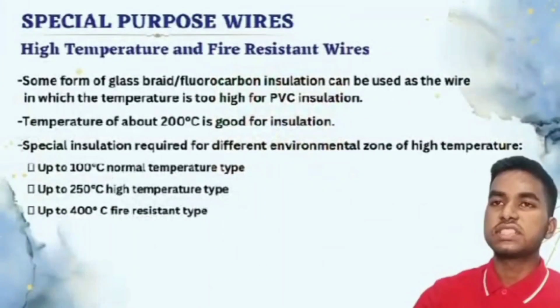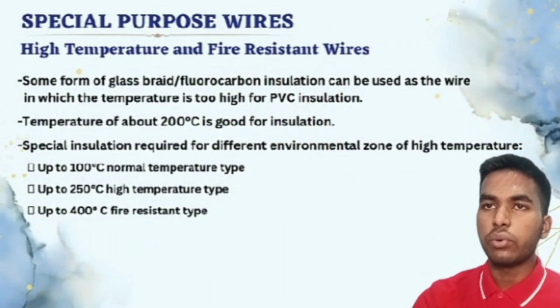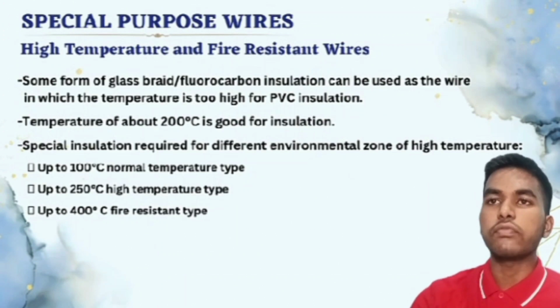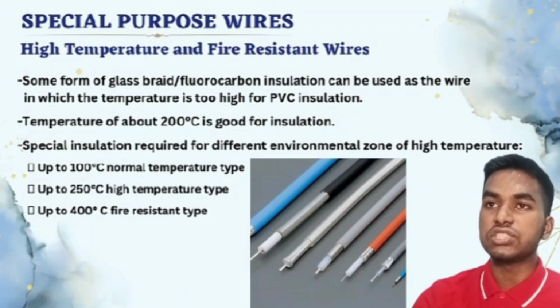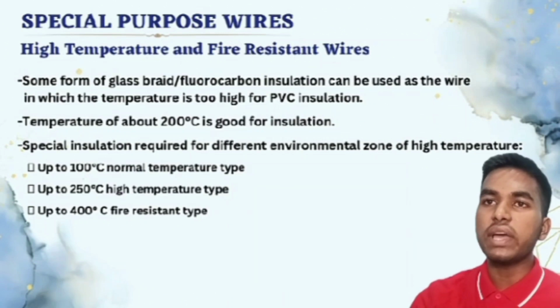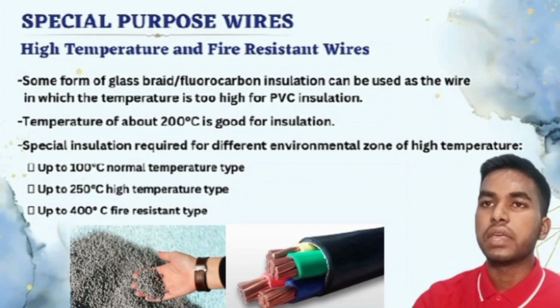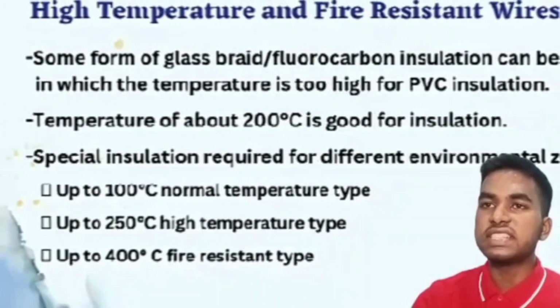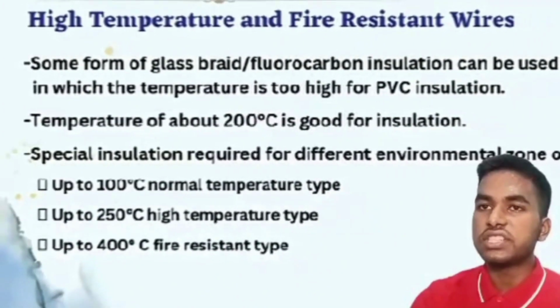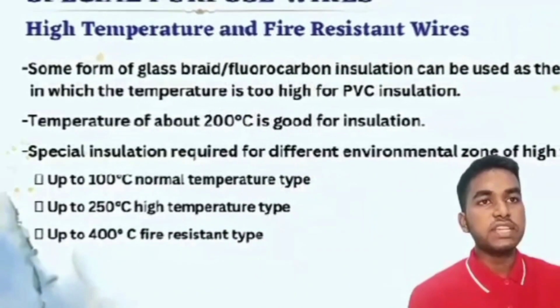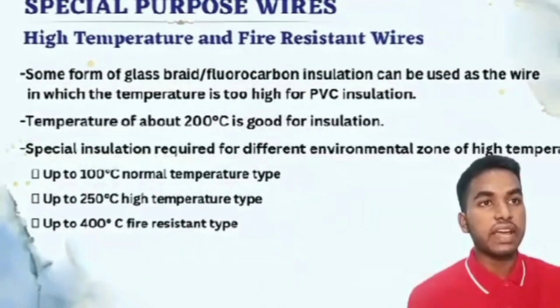So we'll start with special purpose wires, where we have high temperature and fire resistant wires. Some form of glass braid or fluorocarbon insulation can be used as the wire in which the temperature is too high for the PVC insulation.